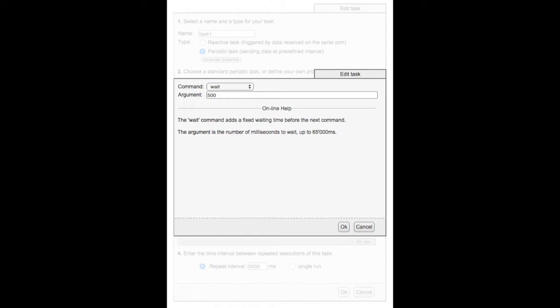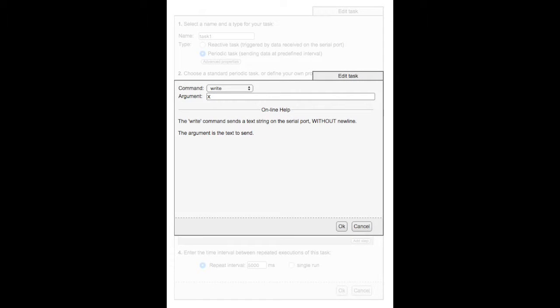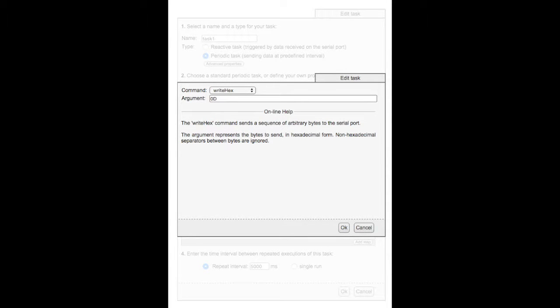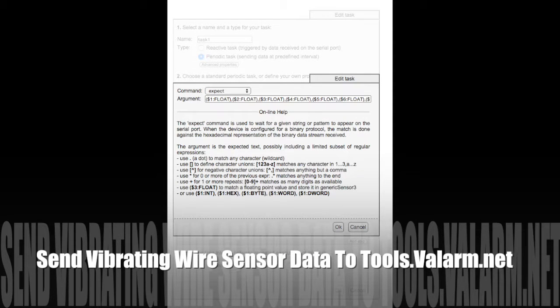With this command, you'll tell the RS232 sensor adapter module to wait 500 milliseconds before sending the next command. Since now your Geokon LC2 data logger is awake and bright-eyed after its siesta, you're ready for a piezometer sensor reading. So we'll write the appropriate command for a vibrating wire data reading: X. To send our request for a piezometer sensor data reading, we'll write hex 0D, aka carriage return, CR. Get yourself ready for Geokon piezometer information.